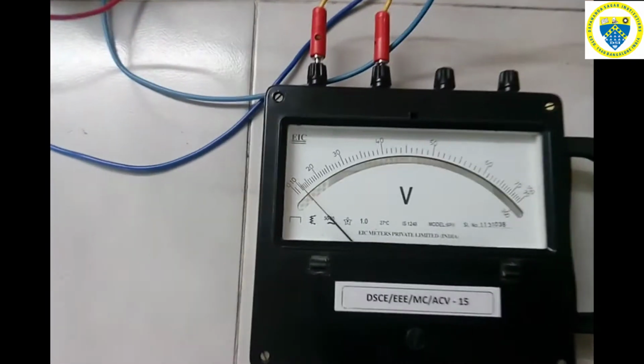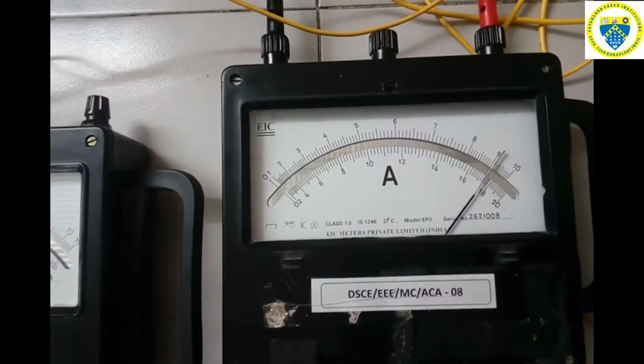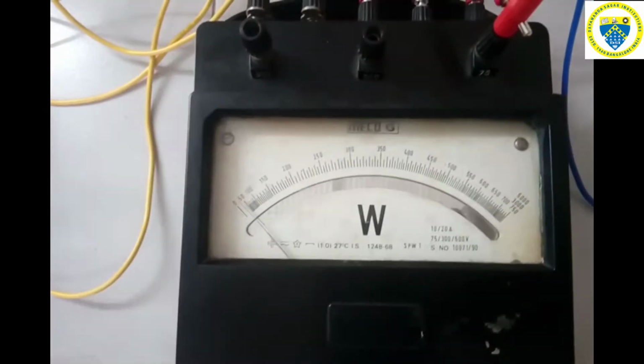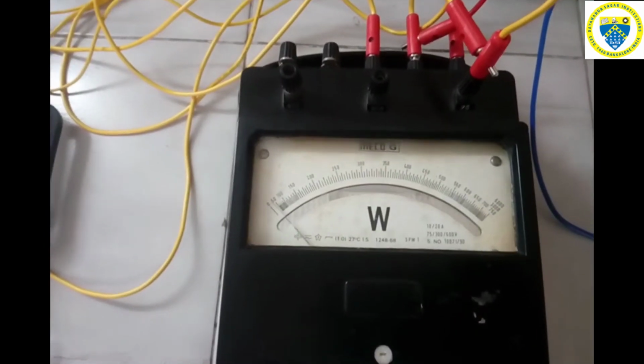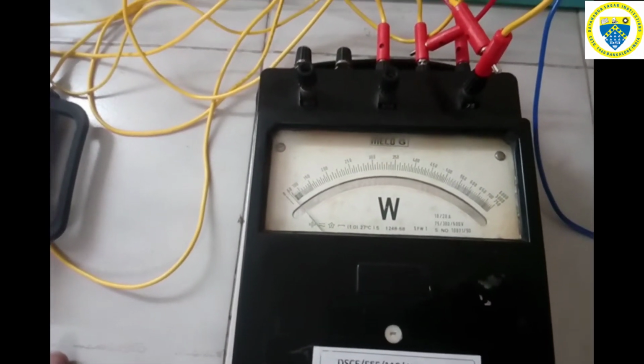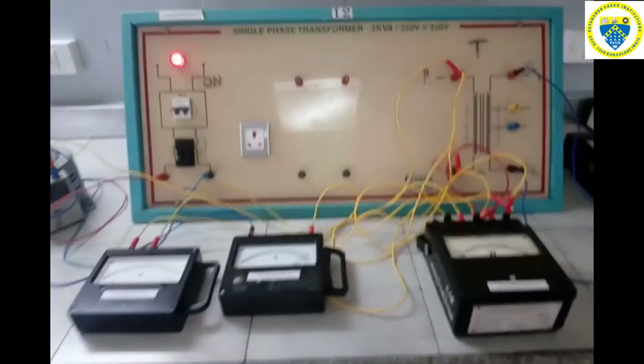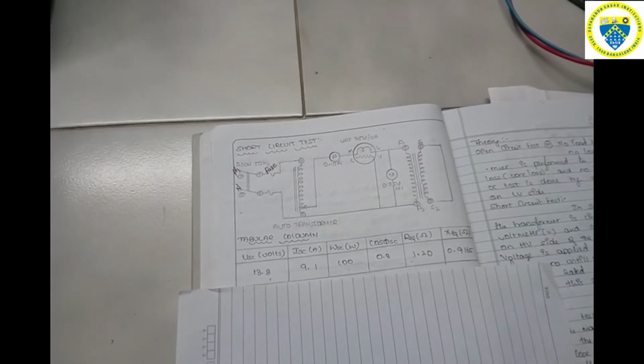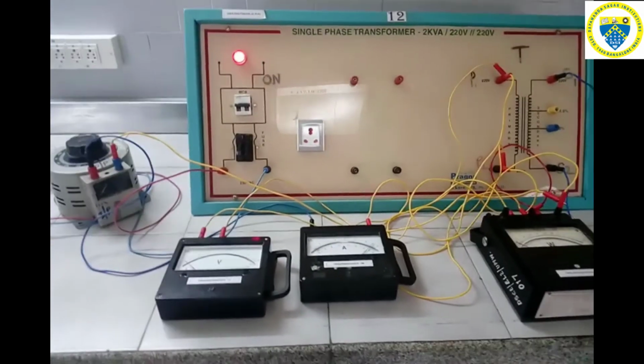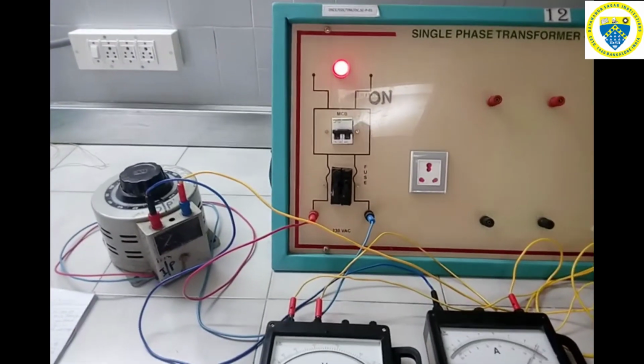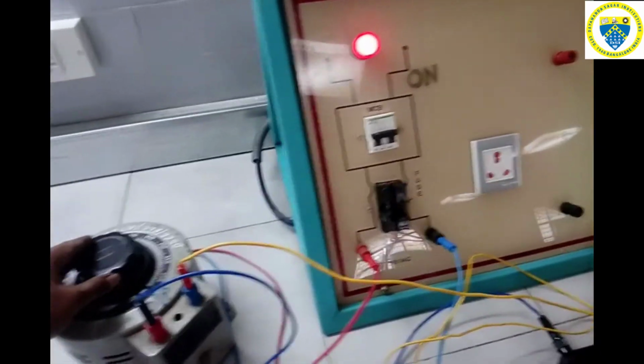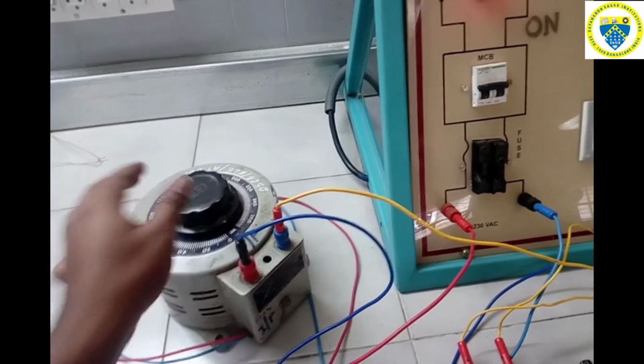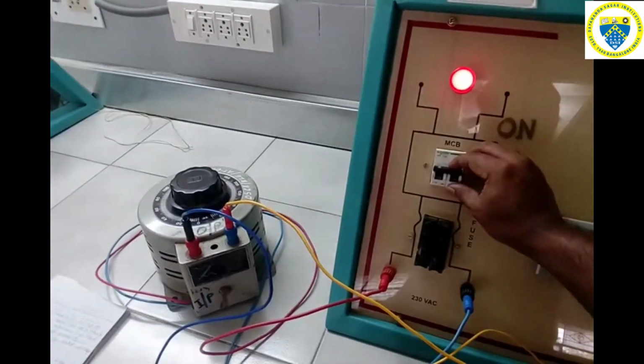After applying the rated current, the corresponding readings of the voltmeter, ammeter and wattmeter should be noted down. Here we are using a unity power factor wattmeter for the short circuit test. The readings are noted down in a tabular column: short circuit voltage, short circuit current and short circuit power supplied to the primary winding of the transformer. The procedure should then be reversed before switching off the mains, that is, bring the auto transformer slowly back to its zero position and then switch off the main supply.